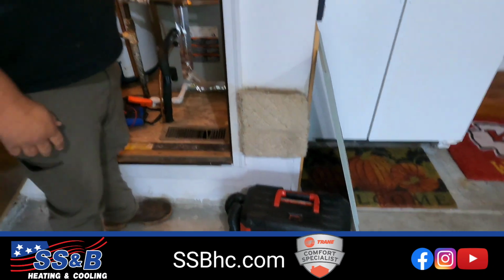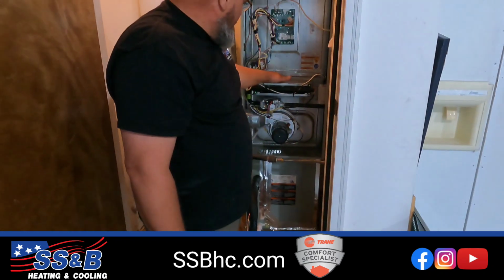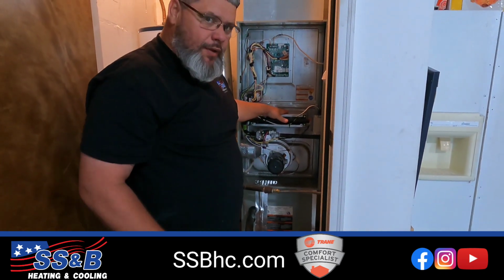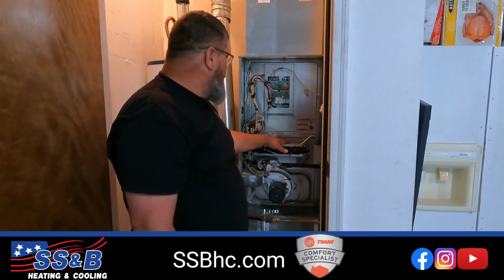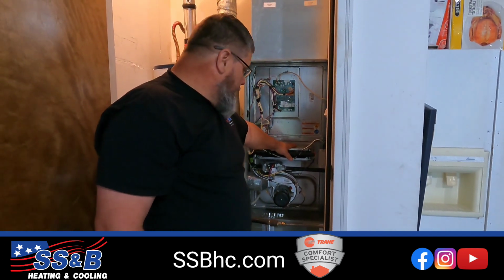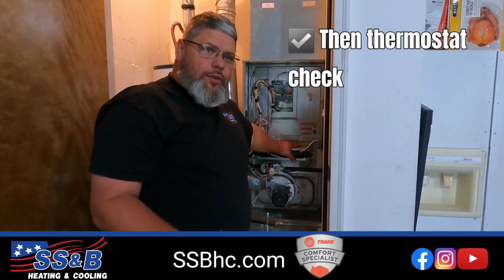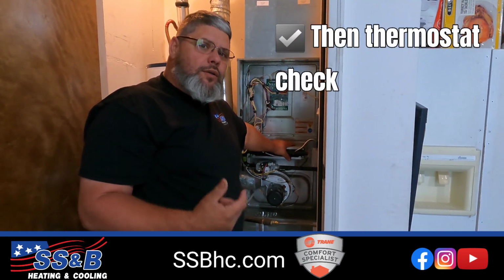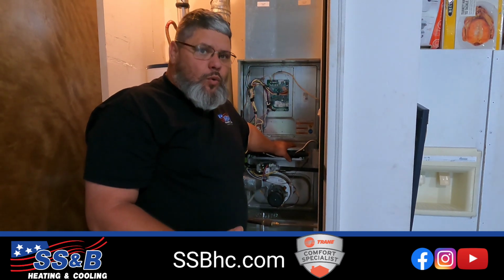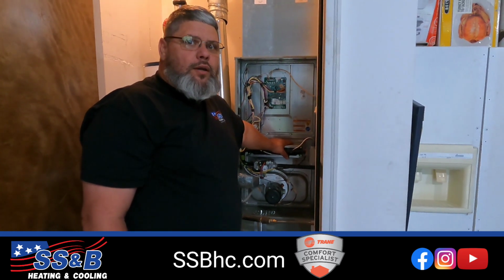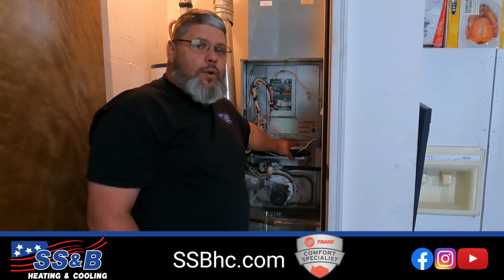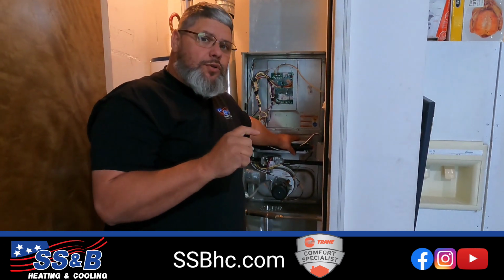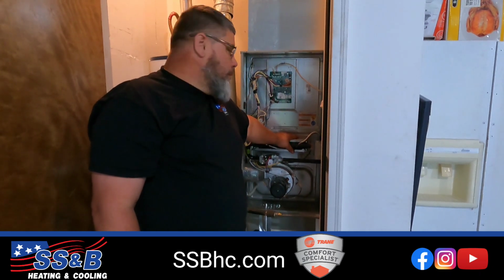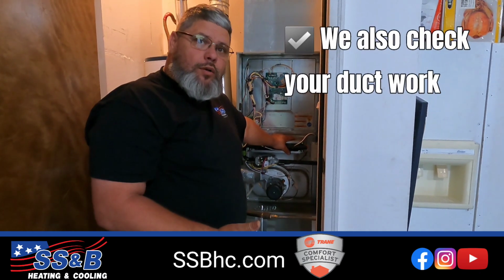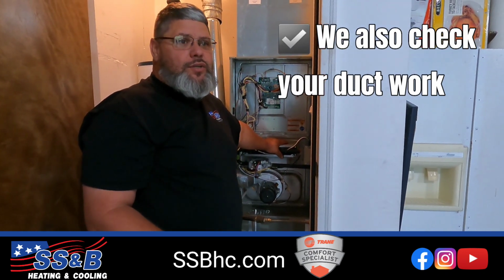So we use a shop vac, and then we're vacuuming all of this out. If there's any buildup inside there, then we shop vac and get all that cleaned out. After we do all of that, we go inside, we'll check the thermostat for correct operation, correct setup, also to make sure that there's no wires that are loose on the backside of the thermostat. We also make sure that we check that the temperature is reading correctly in that space. Part of our maintenance program is also to check the ductwork to make sure that it's sealed, we don't have any leakages in the ductwork.